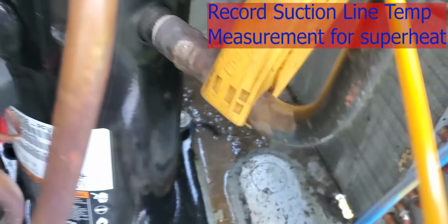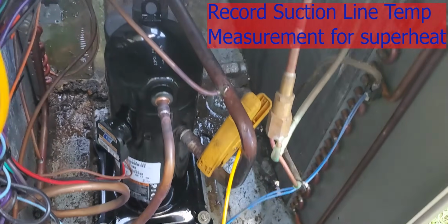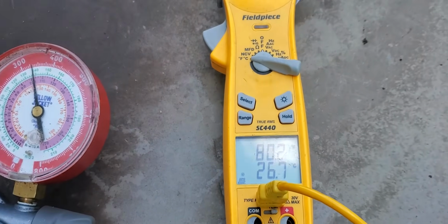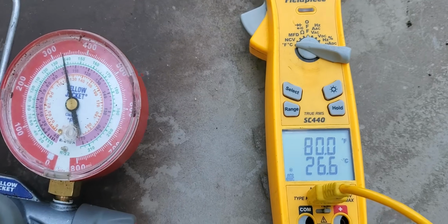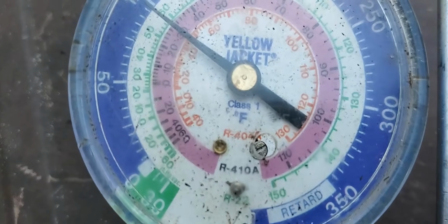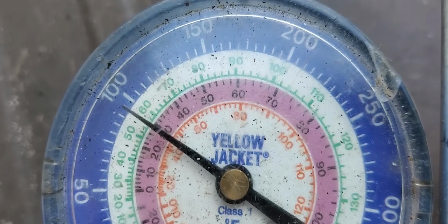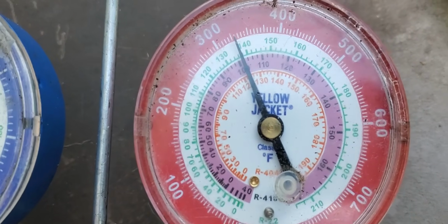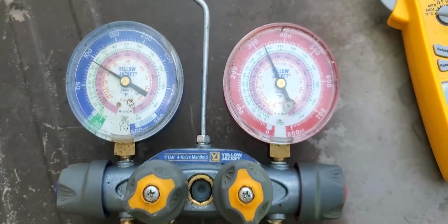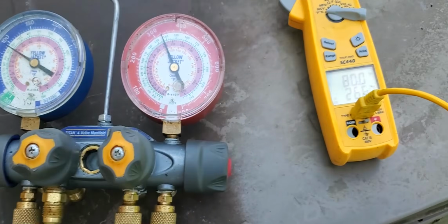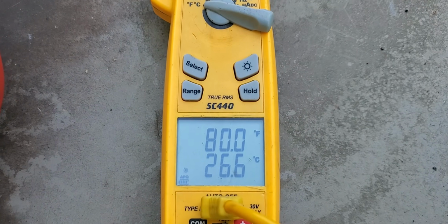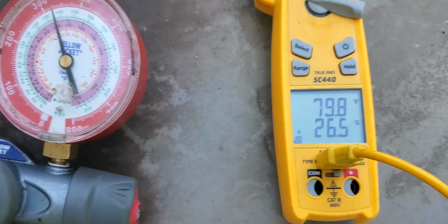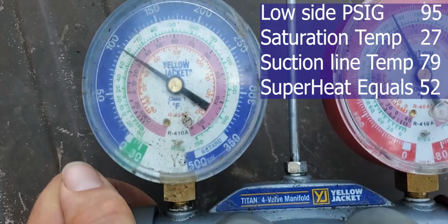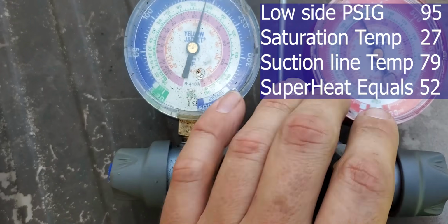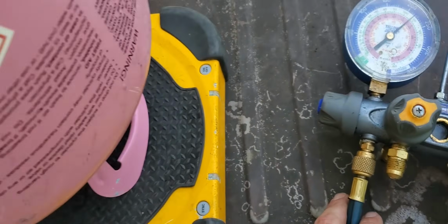Now let's talk about checking refrigerant charge by superheat. You turn on the refrigeration system, you let it run for 10 to 15 minutes. You ensure that there's proper airflow across the condenser and evaporator coils. You measure the dry bulb temperature of the ambient air surrounding the condenser coil. You record that dry bulb temperature. Then you measure the wet bulb temperature of the return air just upstream from the evaporator coil. Record the wet bulb temperature.